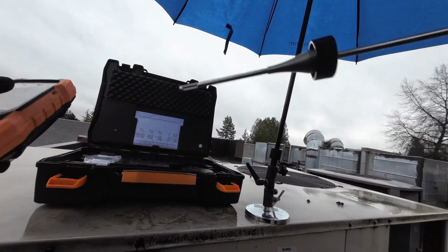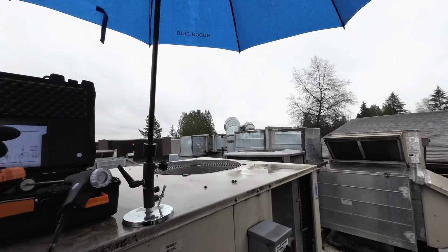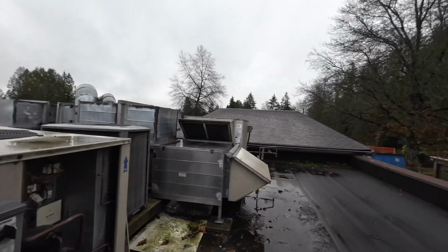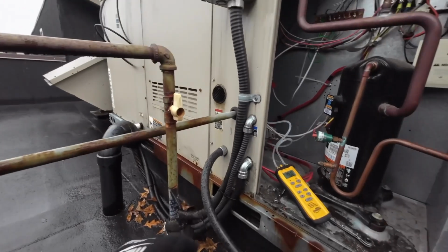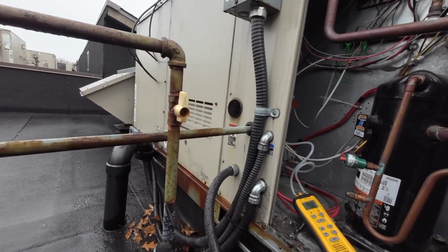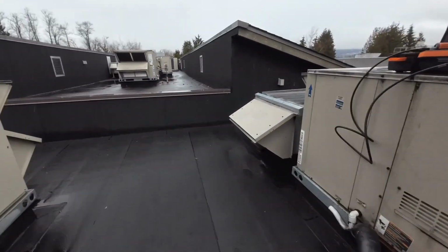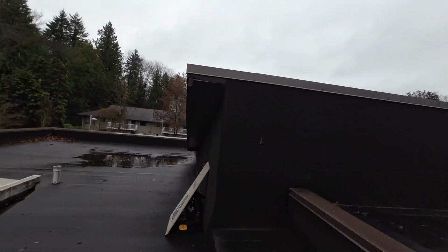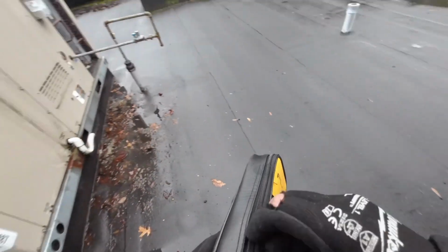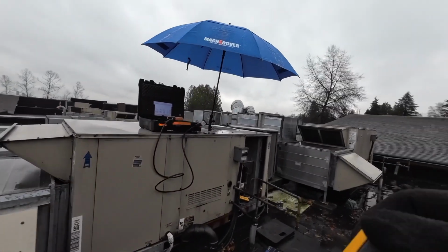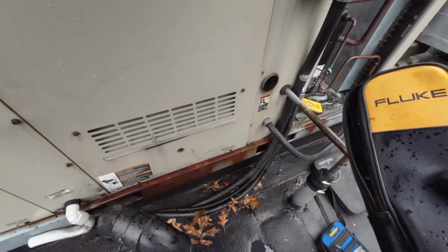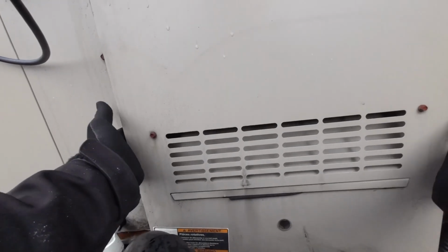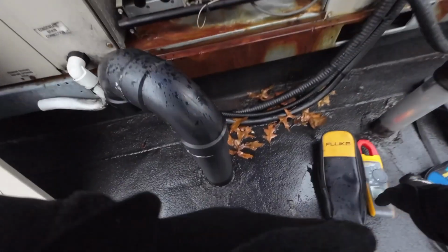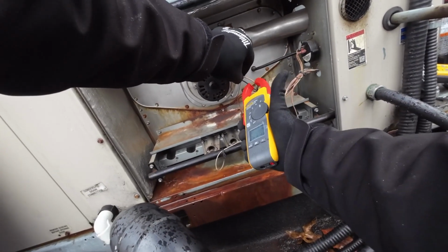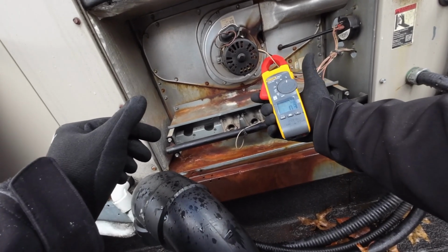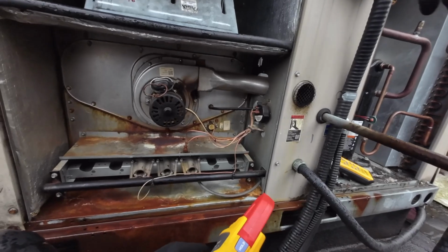A couple things that are going on here. If our gas pressures are good and the inducer's good, I've got either a plugged heat exchanger or a cracked one. We can check those amps right now, just to confirm that. And then that is a plugged heat exchanger, and that could be caused by all sorts of things. The other one, we were at 0.5 of an amp while we were running before. We don't want this on too long, and the fumes that are coming out of here. But we're still good, we're at 0.3. I'm gonna shut this thing down. This thing's got a problem.